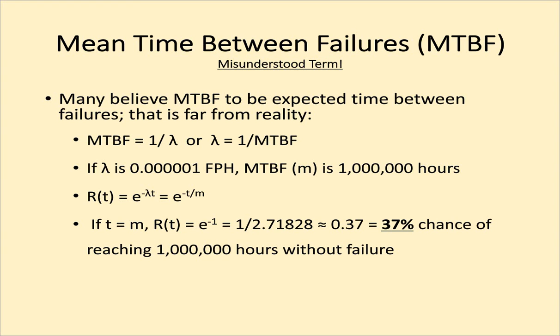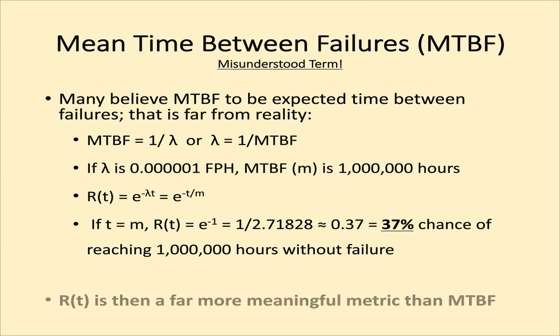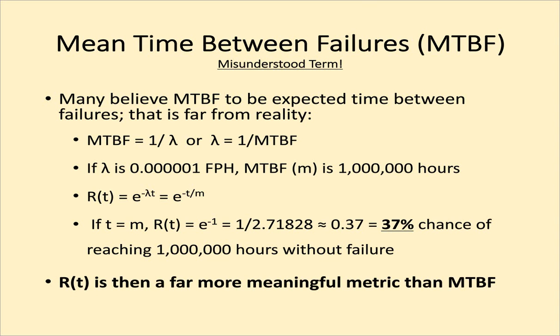That says there's a 37% chance of that hard drive, or whatever the product is, reaching 1,000,000 hours without a failure. That's not a very good indicator to me. So I believe that the reliability metric is a much more meaningful number than MTBF. I don't have any proof of this, but I've always believed that MTBF was developed as a marketing tool.